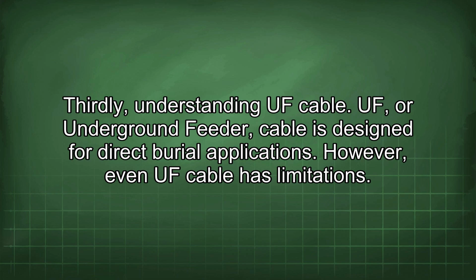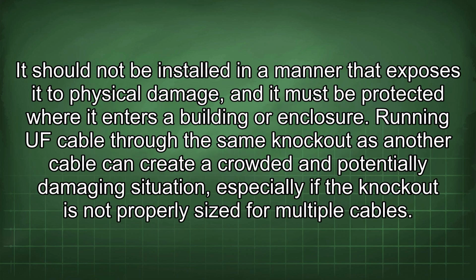Thirdly, understanding UF cable. UF, or underground feeder, cable is designed for direct burial applications. However, even UF cable has limitations. It should not be installed in a manner that exposes it to physical damage, and it must be protected where it enters a building or enclosure. Running UF cable through the same knockout as another cable can create a crowded and potentially damaging situation, especially if the knockout is not properly sized for multiple cables.